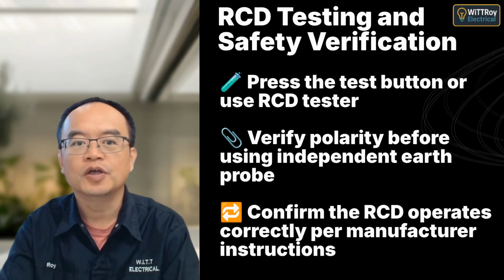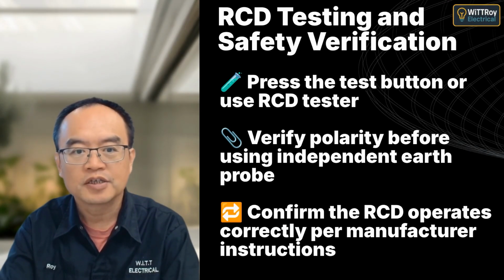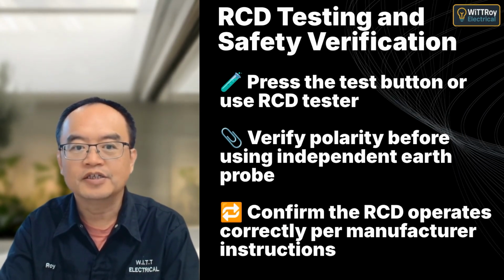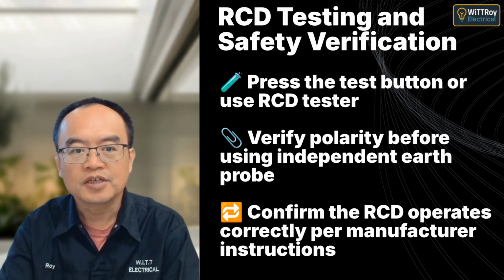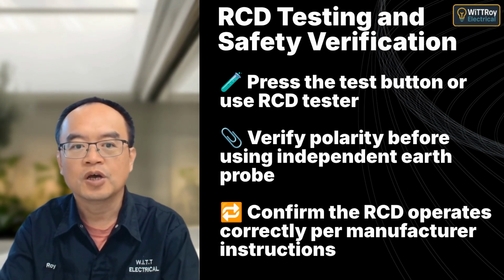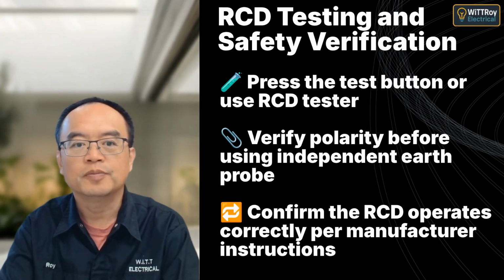Use the test button or an RCD tester to confirm the RCD operates correctly. AS/NZS 3017 requires functional testing only, not measuring trip time. Always check polarity before using an independent earth probe.